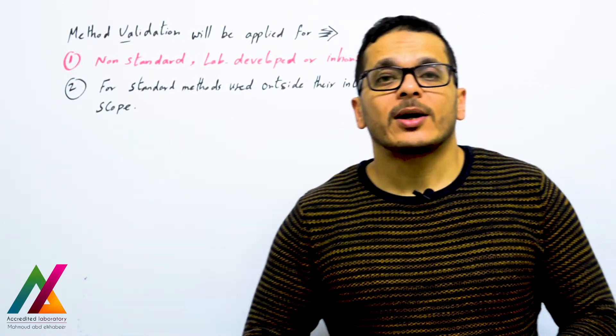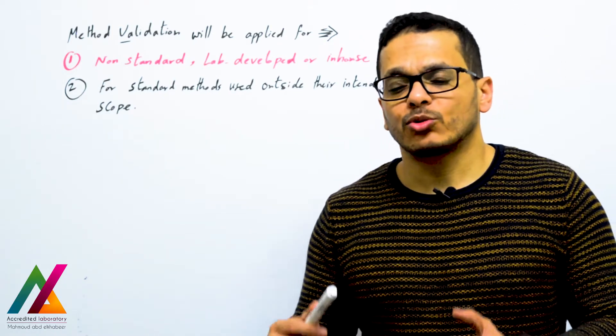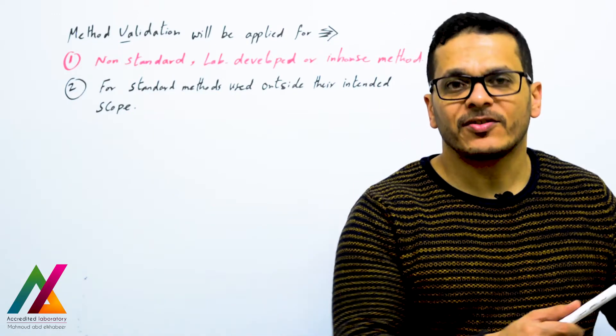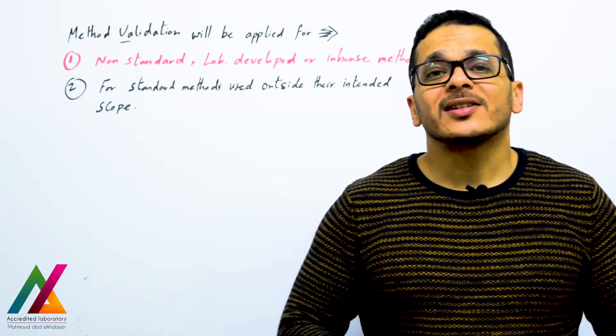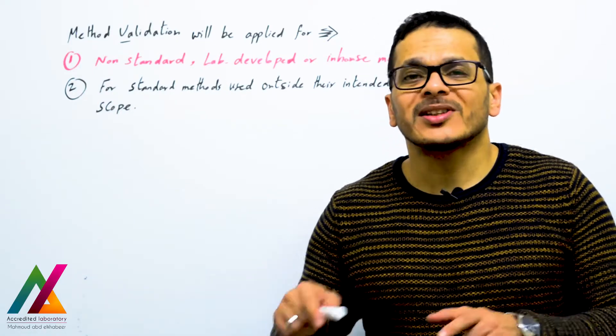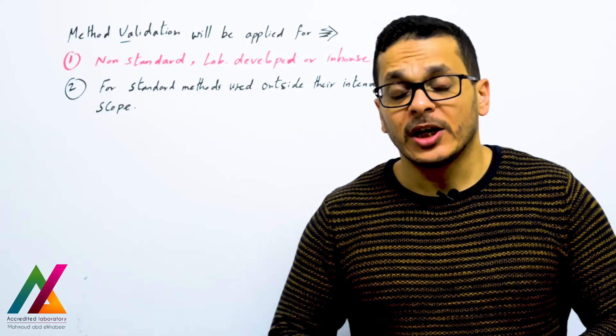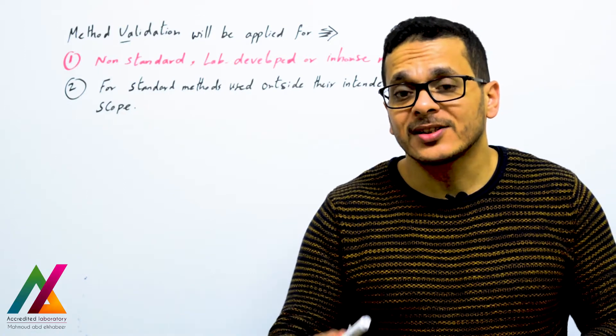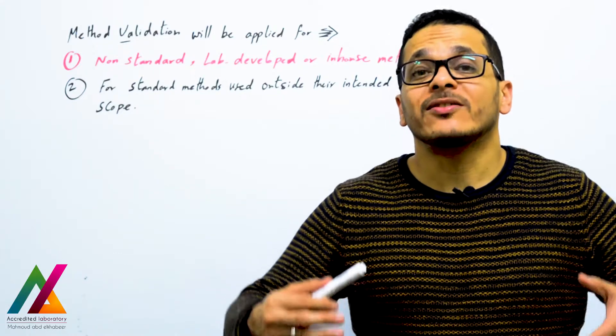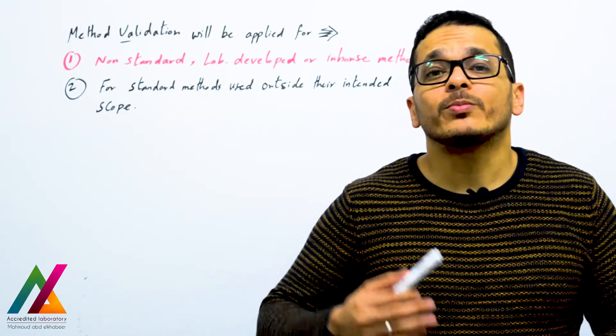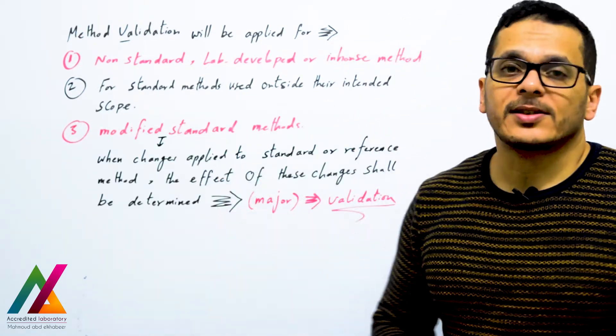Method validation also applies for standard methods used outside their intended scope. If you have a reference method to analyze target analytes in a specific matrix, but you want to use it in a completely different matrix, you will adapt this method to extract your target analytes from that matrix. Because of this adaptation, you should perform validation. It also applies for modified standard methods.